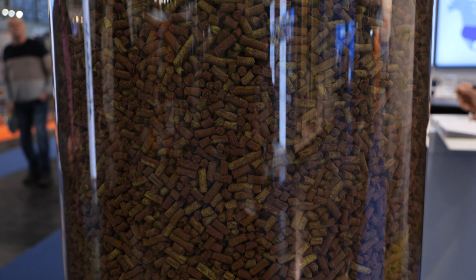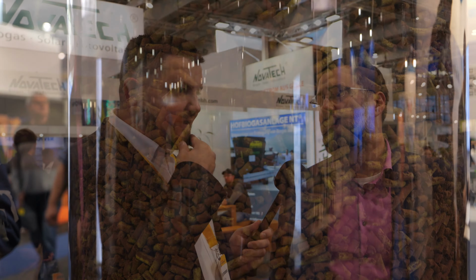Yeah, the idea is to have the shower effect inside the vessel, inside the filter tank. So we have the smaller ones on top. With this we create a little bit of pressure drop inside, and caused by this pressure drop we have a better gas distribution in the lower levels. Okay, so it's for more effective use of the pellet. And this is the way it should be in the filter.